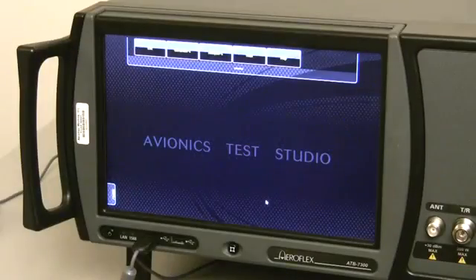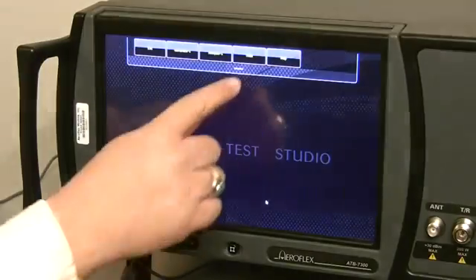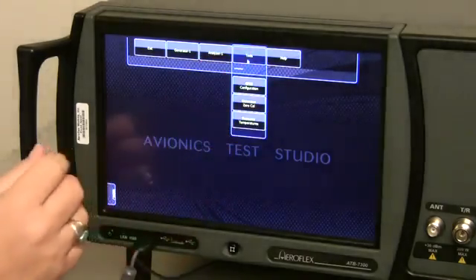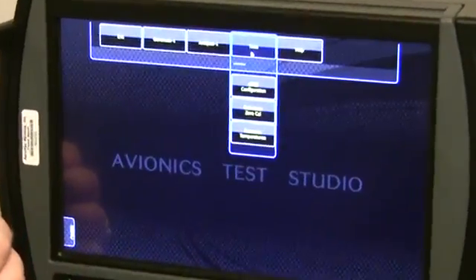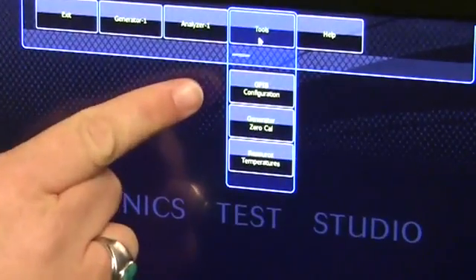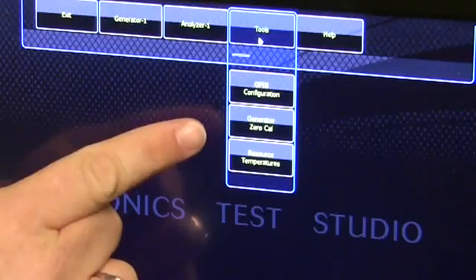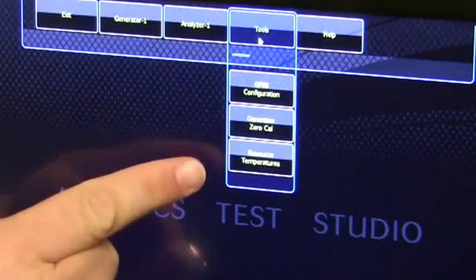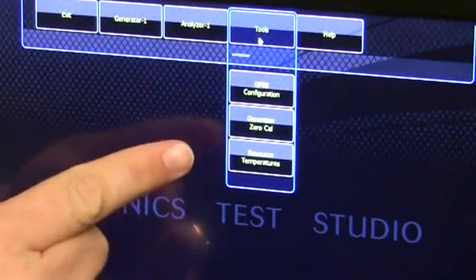If you touch the Tools selection, there are three sub-selections: GPIB configuration, Generator 0 Cal, and Resource Temperatures.